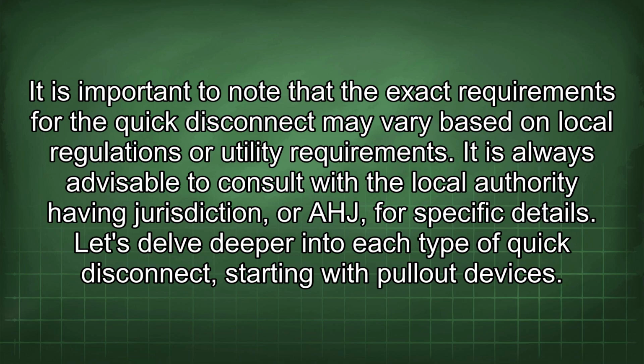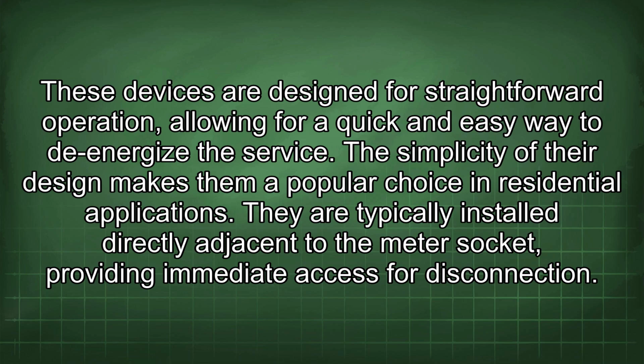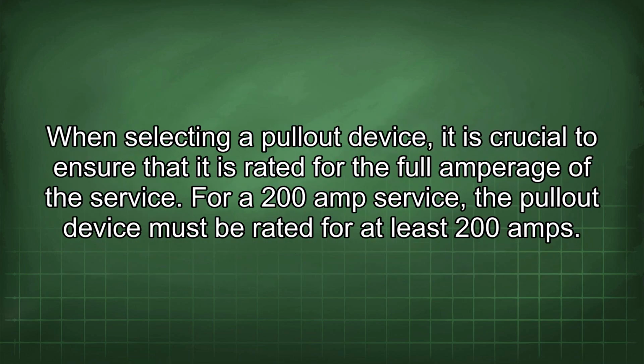Let's delve deeper into each type of quick disconnect, starting with pullout devices. These devices are designed for straightforward operation, allowing for a quick and easy way to de-energize the service. The simplicity of their design makes them a popular choice in residential applications. They are typically installed directly adjacent to the meter socket, providing immediate access for disconnection. When selecting a pullout device, it is crucial to ensure that it is rated for the full amperage of the service. For a 200 amp service, the pullout device must be rated for at least 200 amps.